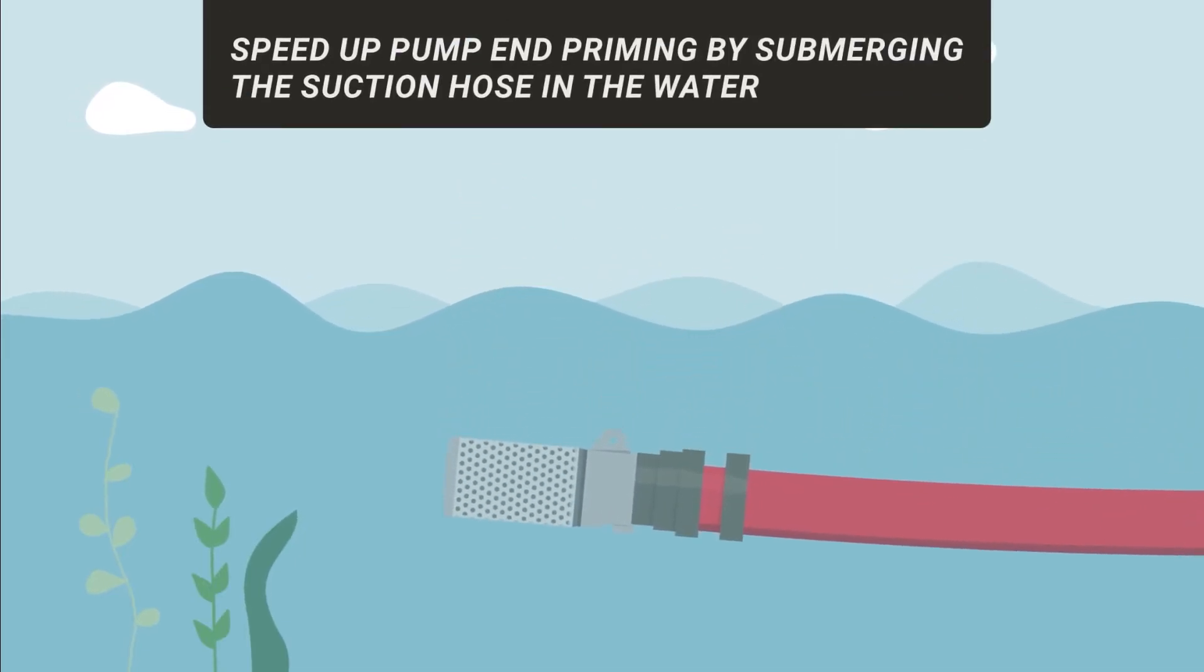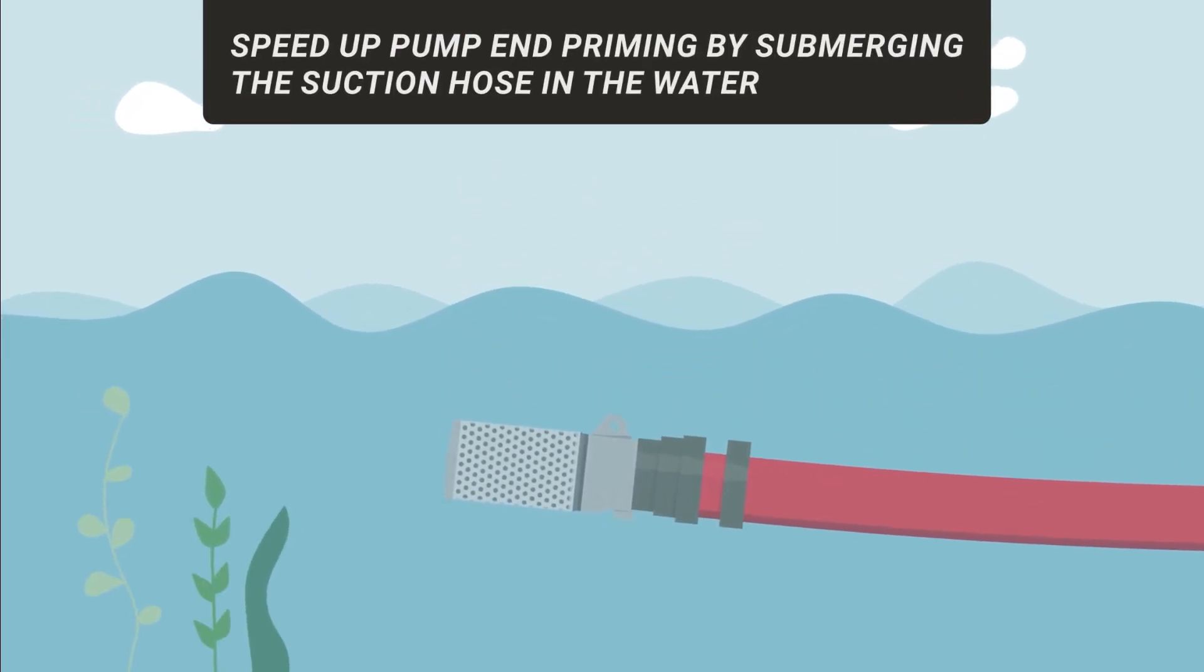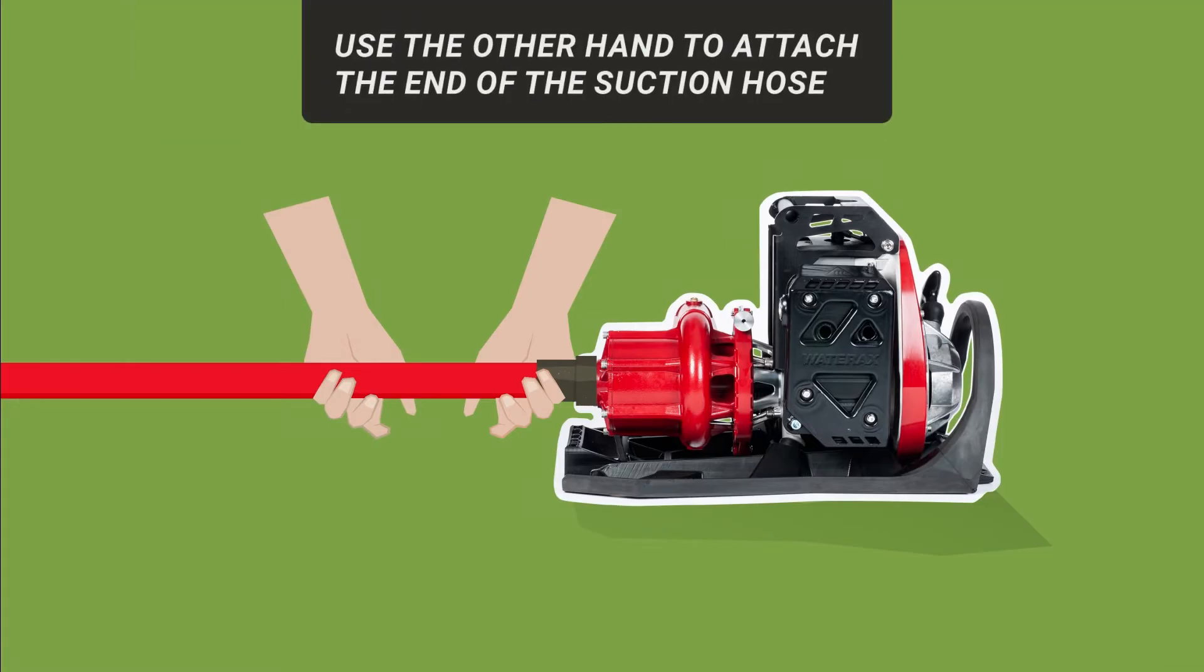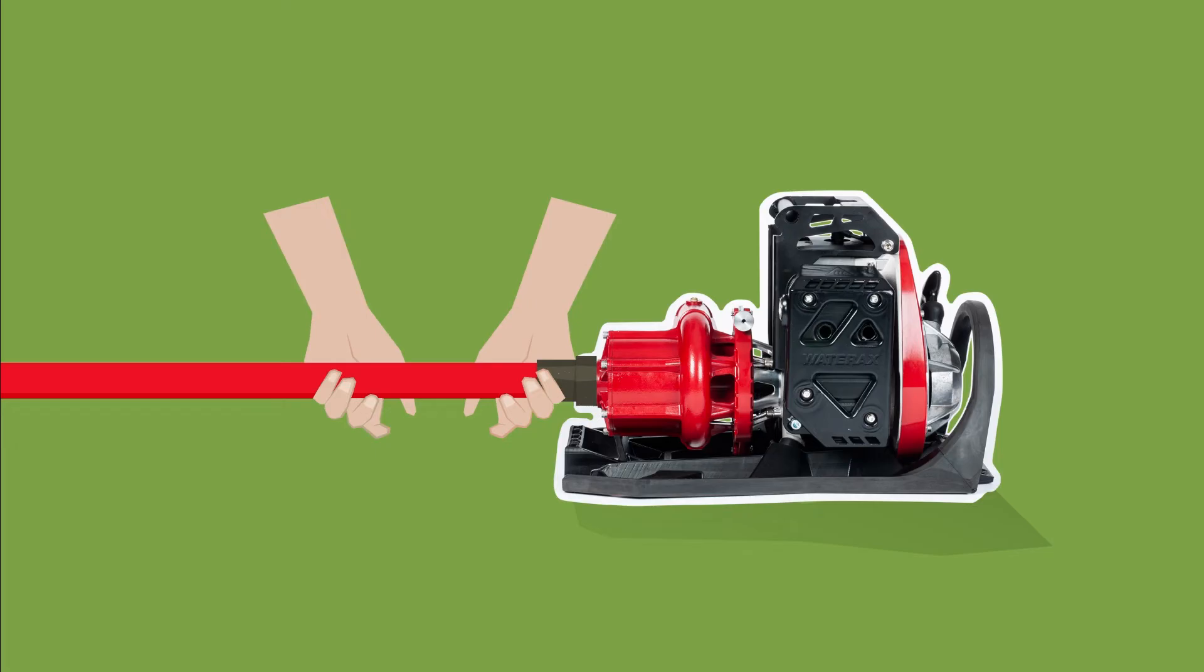Speed up pump end priming by submerging the suction hose in the water before attaching the pump intake. Use one hand to keep the suction hose level and straight to take pressure off the threads. Use the other hand to attach the end of the suction hose to the pump intake. Hand tighten as much as possible.